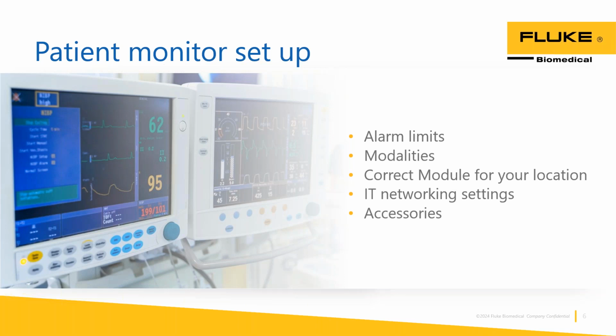And this is something that we do see a lot of, where they'll change out monitors on the floor, things will get changed out, or you have a patient who transfers to the hospital, the monitor gets carried with them, and it might not get put back into the same place. So in part of the PM sequences, it's really making sure that we do have these setups correct, and it does have the correct settings. I was at a facility here a few months ago, and we were troubleshooting through a few things and opened up the drawer to find an IBP cable, and the biomed's looking down and scratches his head and goes, listen, we haven't even had these monitors in months. Why is this cable still here?